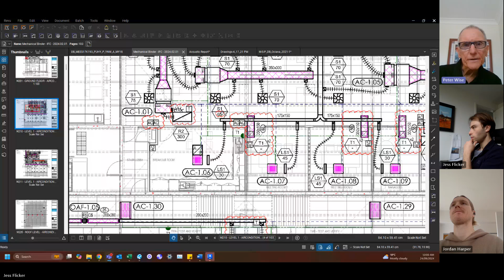I said last week that noise sources are additive. So if you've got a noise source, the cassette unit is, let's say, already 30 dBA, but you've got another noise source from the outside air which might be another 30 dBA. The result, if they're the same sound level, and depending on how far apart they are, will increase the noise level in the space.